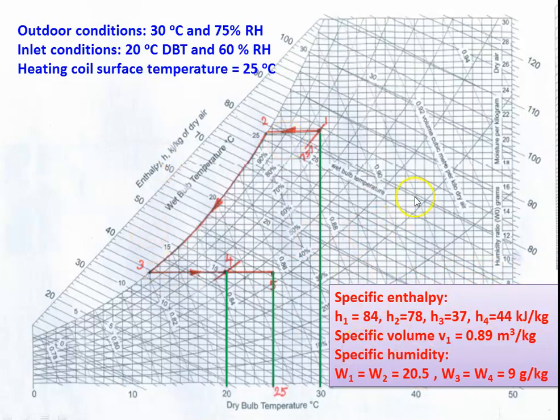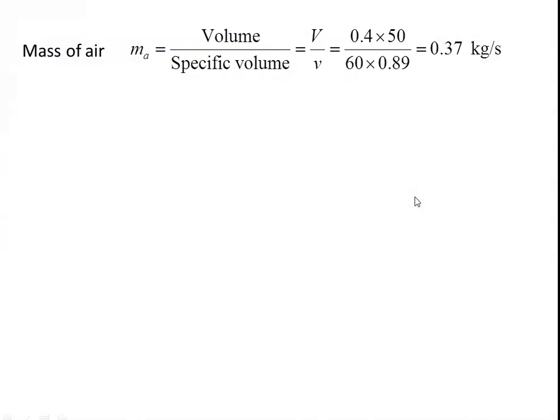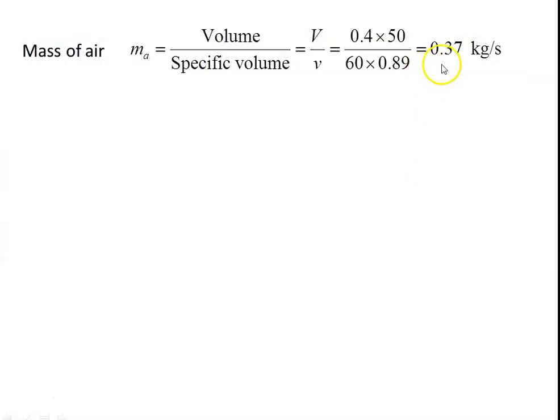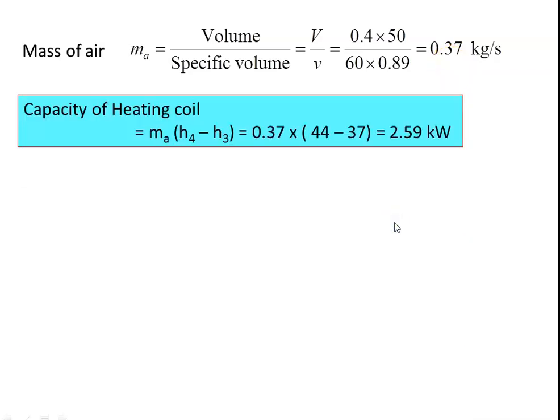Calculate the mass flow rate of air: volume divided by specific volume = (0.4 × 50) / (60 × 0.89) = 0.37 kg/s. Capacity of heating coil = ma × (h4 − h3). The air is heated from initial condition h3 to final condition h4.